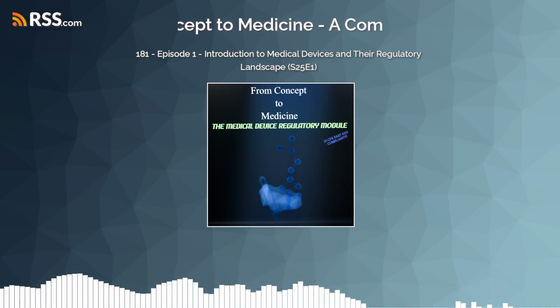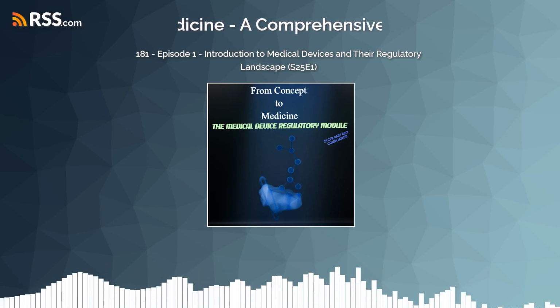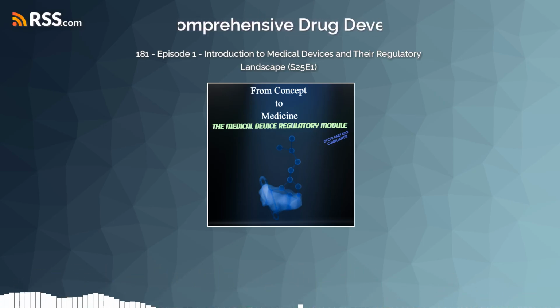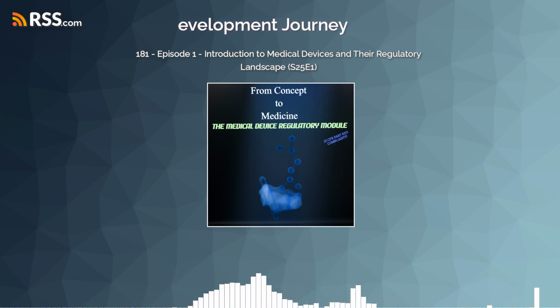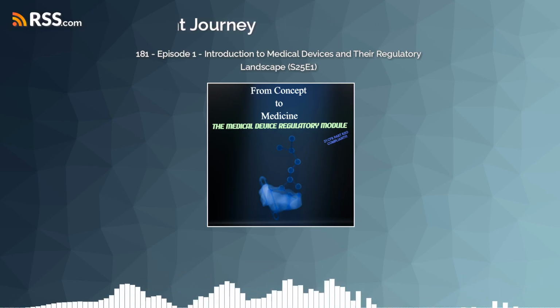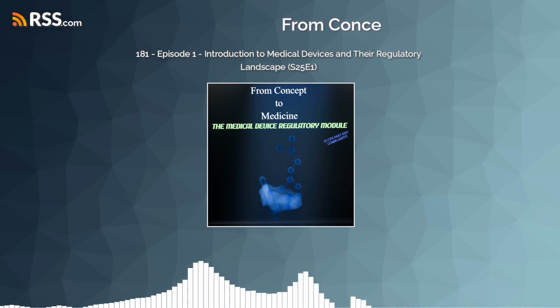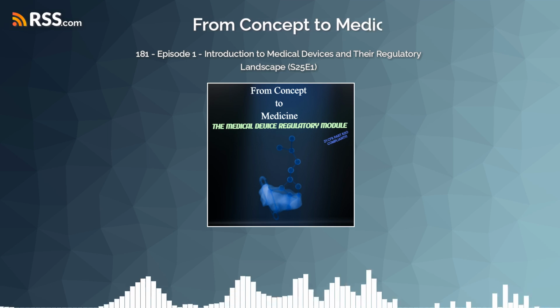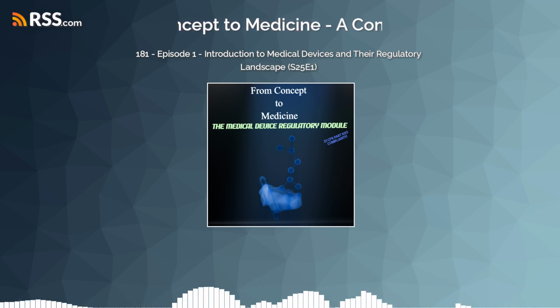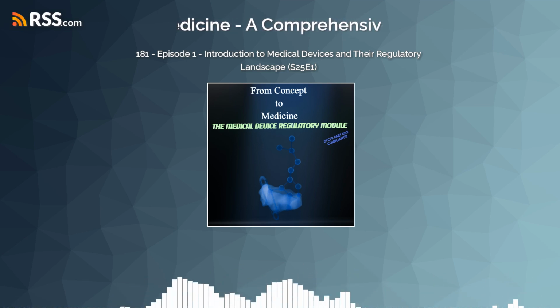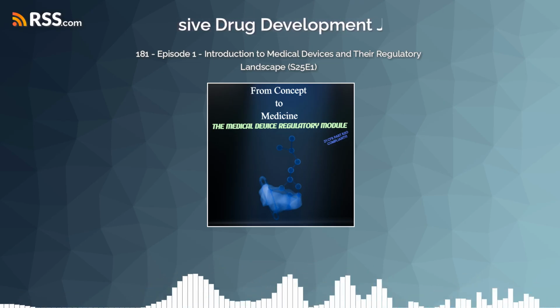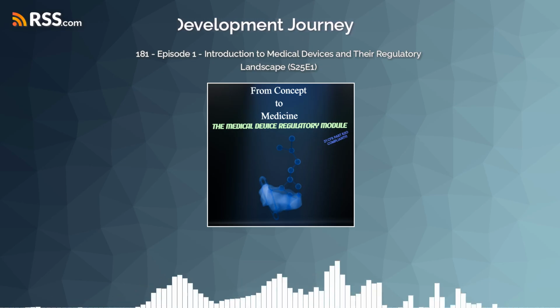And I imagine, similar to the device classes, not all device studies carry the same risk for the participants. That's a key distinction the FDA makes. They differentiate between significant risk and non-significant risk device studies. Okay, SR versus NSR. Exactly. A significant risk, or SR device study, involves an investigational device that poses a potential for serious risk to the health, safety, or welfare of a subject. Think implants, devices supporting or sustaining life, or those used for diagnosing or curing serious conditions.